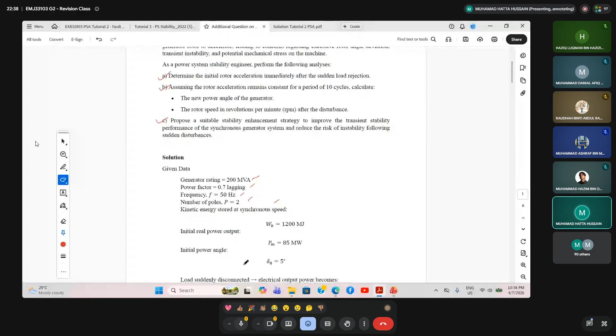So actually this is how you solve this kind of question. You just write back the rating, the power factor, the frequency, number of poles, kinetic energy stored at synchronous speed, which means WK. And then we have the initial real power output, PM equal to 85 megawatt, and the initial power angle, which means delta naught. Initial power angle delta naught equal to 5 degree.